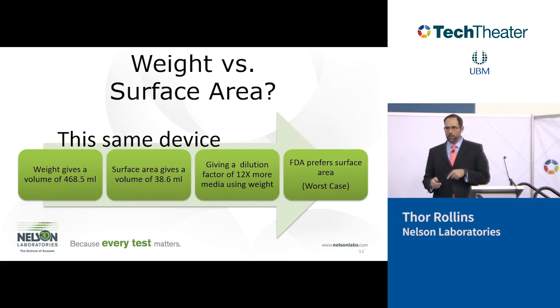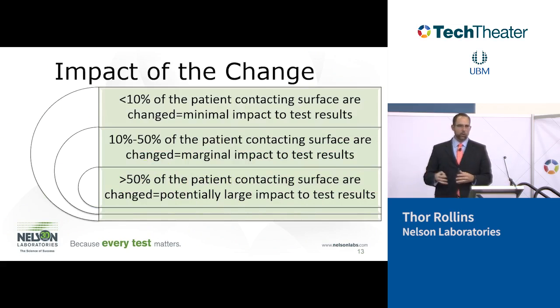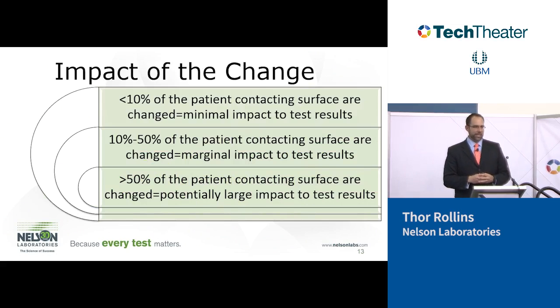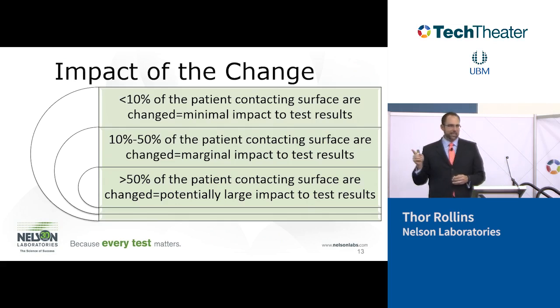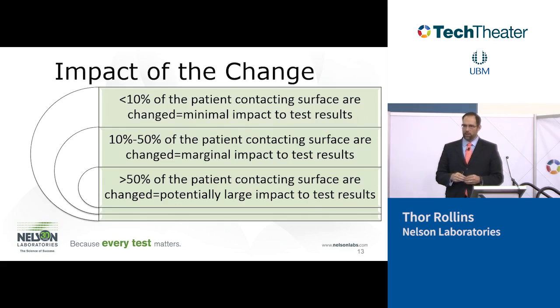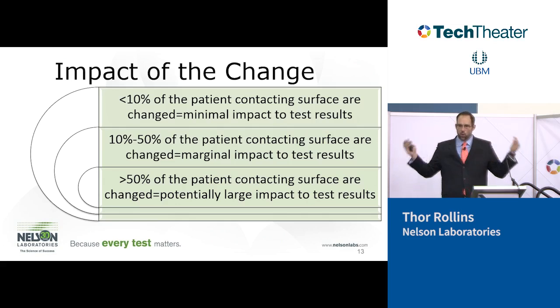That same approach needs to be applied to the impact of a change to a device. What's the impact of that change on the surface area of that device? That will help me decide what kind of testing we might need to do, or what evaluation would have to be done to evaluate that impact, okay? So this is the impact. We use the same kind of ratio thinking per the standard. If the change is less than 10% of the total patient contacting surface area, then the impact to the patient is very small, and we can get by with a more aggressive type of test setup.